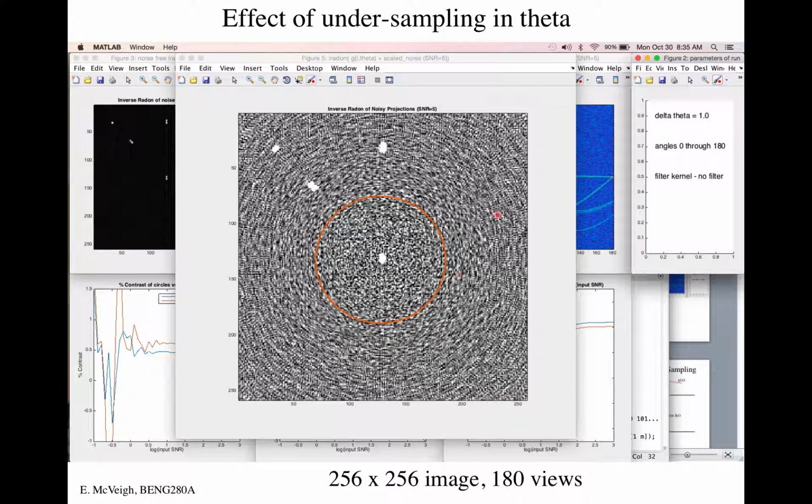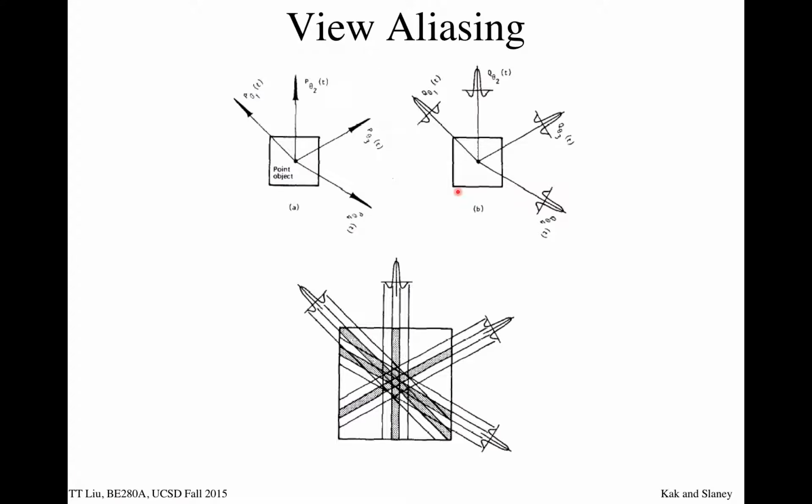And the question is, inside this picture, what field of view has been adequately sampled? And it certainly looks like it's a circle about this big, right? Because this stuff still looks artifacty and it's blurry in this direction. So this is called view aliasing and/or undersampling.